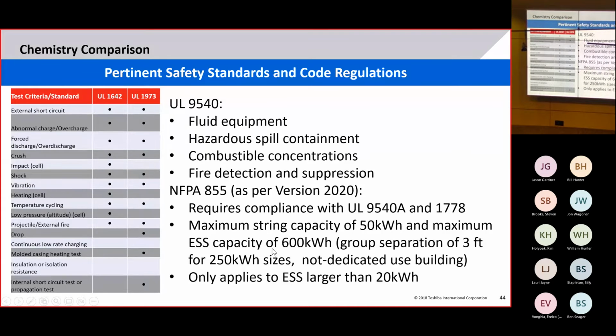With NFPA 855, we also get a waiver for the 600 kilowatt max per hour for a non-dedicated building as far as LTO is concerned, because there's no fire and no smoke, so we've been able to secure those waivers. That doesn't mean we'll get them in every jurisdiction, since AHJs differ from municipality to municipality. What we've found is that if we work with a fire engineer who reviews the UL 9540 test results, designs around them, and stamps the submission to the AHJ, they're more willing to consider the waivers, because now someone professionally liable is putting their name on it and carrying the risk.